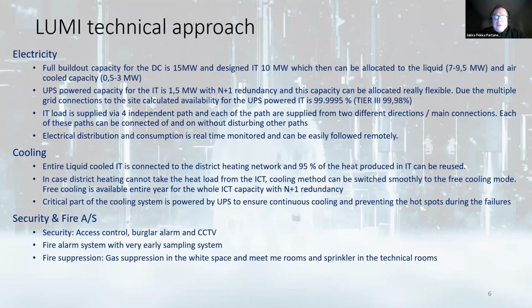Due to multiple grid connections, the site calculated availability for UPS powered IT is five nines. IT load is supplied via four independent paths. Each of the paths is supplied from two different directions, so main connections to the cabinet. Each of these paths can be connected on and off without disturbing other paths. And electrical distribution and consumption is monitored in real time and can easily be followed remotely. So those were the electricity design principles.